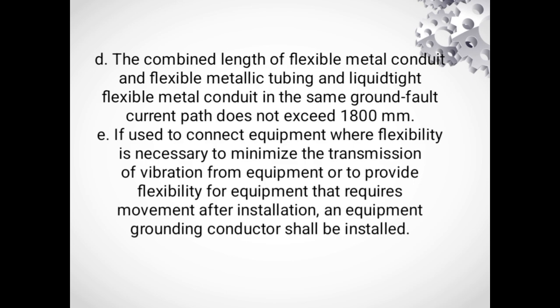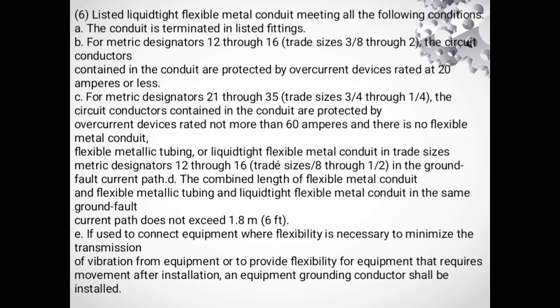Specific equipment such as motor, switchgear, and switchboard need all ground to prevent short circuit. You can use everything. 6. Listed liquidtight flexible metal conduit meeting all the following conditions. A. The conduit is terminated in listed fitting. B. For metric designator 12 through 16, trade size 3/8 through 1/2, the circuit conductors contained in conduit are protected by overcurrent devices rated at 20 amperes or less.